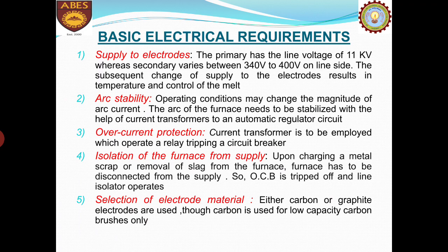Also, a second isolator is provided between the mains and the oil circuit breaker. This is necessary to disconnect the oil circuit breaker from the line from a maintenance and repair point of view as well. Now, frequent tripping carbonizes the oil of the breaker and burns the contacts, which have to be taken care of periodically. Now lastly, the selection of electrode material.